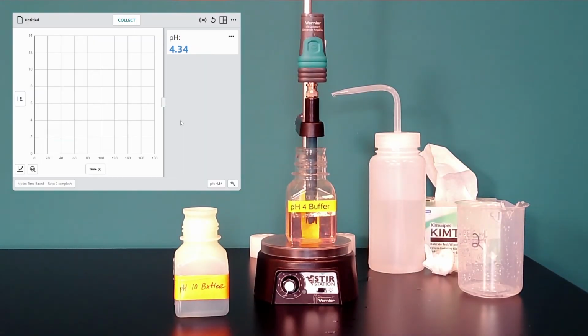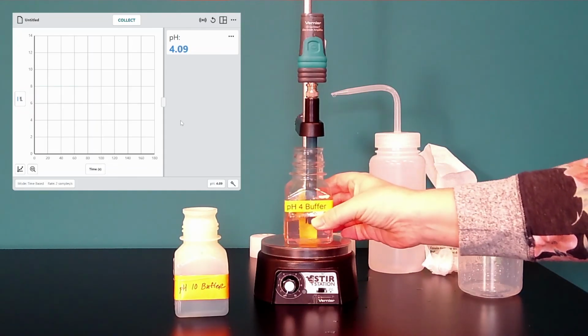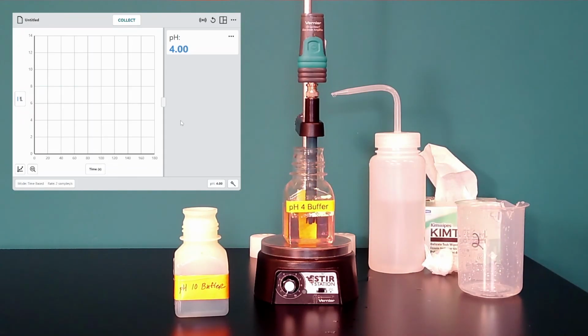And it will take a few seconds to stabilize again. This is a big jump for a pH sensor. And it does help if you provide a little bit of agitation or stirring to the solution. And there it is, back at pH 4. Now my pH sensor is calibrated and ready to use, and the calibration is automatically stored to the sensor.